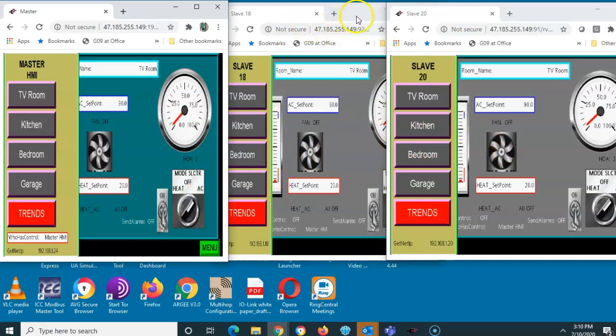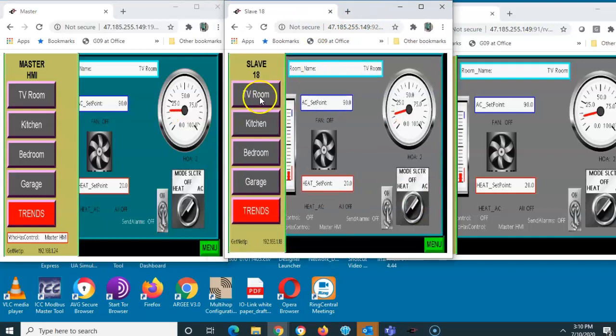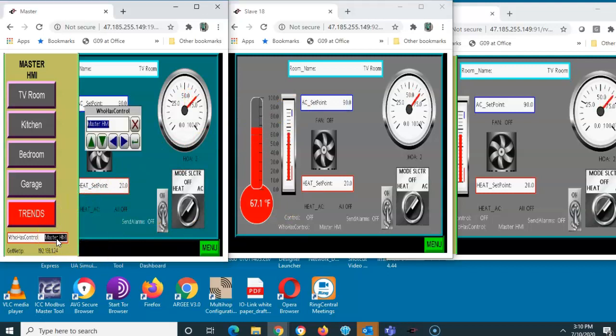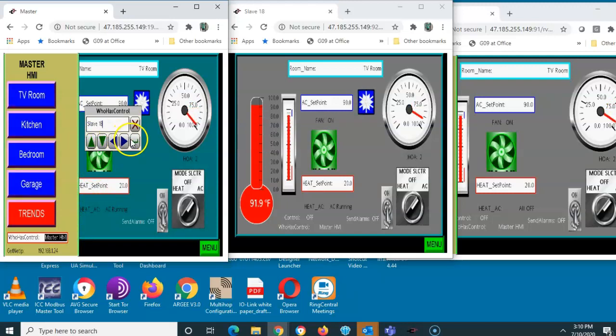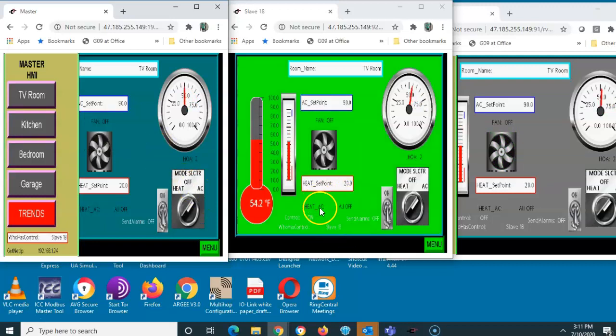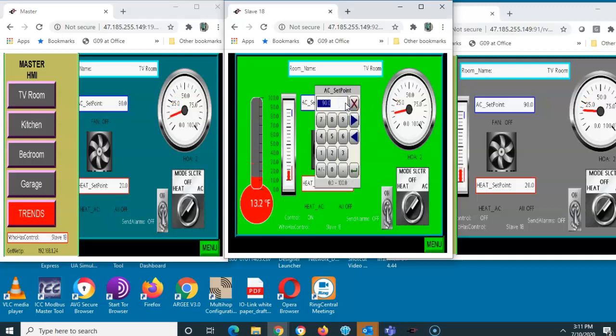I can leave control as the master HMI or I can dedicate these other screens to have control. If I go over to slave 18 and click on the TV room, clicking nothing happens — nothing is editable. What I've got to do is on the master, change 'who has control' to give control to slave 18. When I hit enter, the background turns green indicating that this HMI now has control.